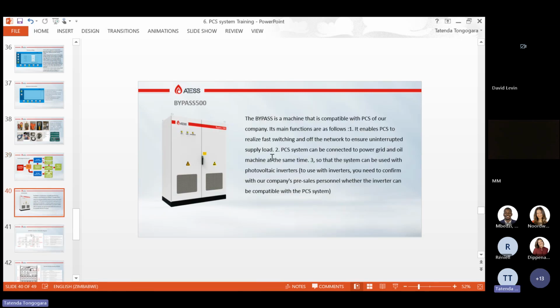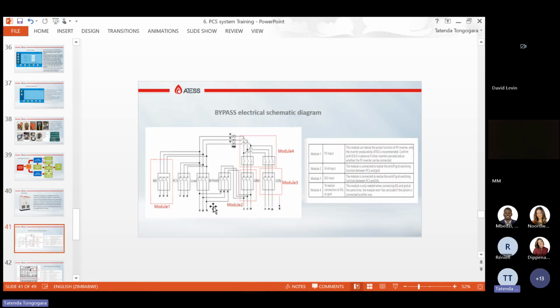So the bypass, this is our bypass machine. This is the second diagram. As I was saying, we have the inverter module. This is where you connect your PV inverters. The output from PCS, you connect it here, and then you have your load in the bypass breaker. You have your grid input, your generator input. And then module number 4, these are just contactors that will distinguish between generator and grid, so that if you set your system to export to grid, it will not export whilst the generator is running.